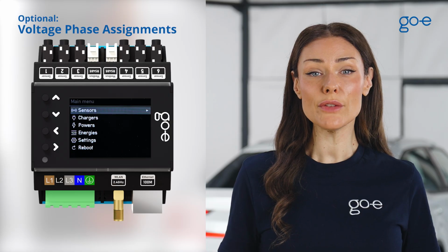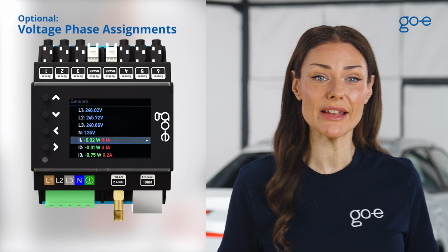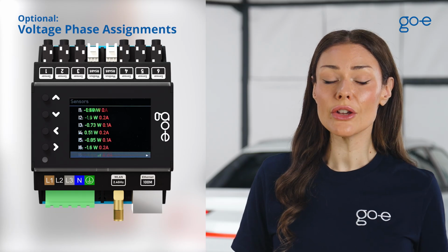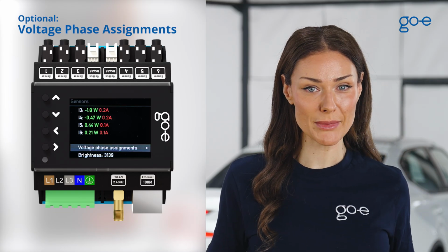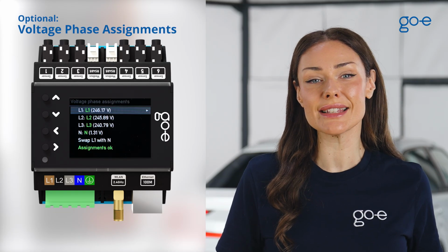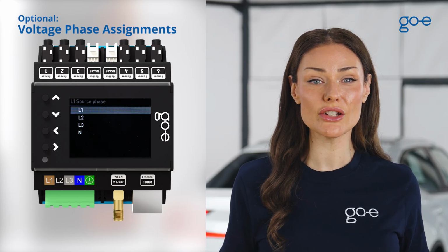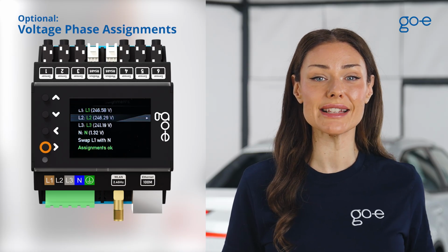They're only needed if the voltages at the controller's connection terminal are not wired in the same order as the phases in your distribution board. If your sensors are already set up correctly, you don't need to change anything here. If you select Sensors in the main menu and scroll all the way down, you'll find the voltage phase assignments.